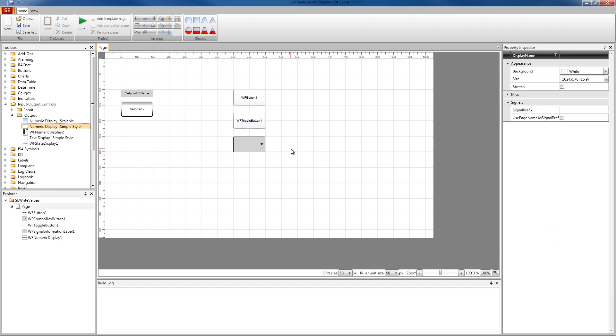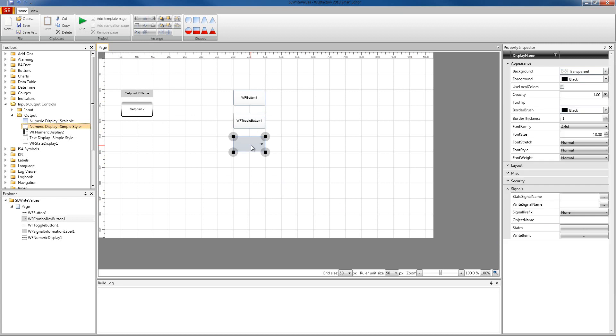Now comes the more difficult part — by difficult I mean we're going to have to make a few more settings. As you can see in the signal category in the property inspector when we select the combo box button, we have the state signal name and the write signal name. The state signal name allows us to link a signal to our combo box button, and this signal would change the state of our combo box. But for this example we don't need any states for our combo box, so we're just going to focus on the write signal name. So I'm going to put here set point two.